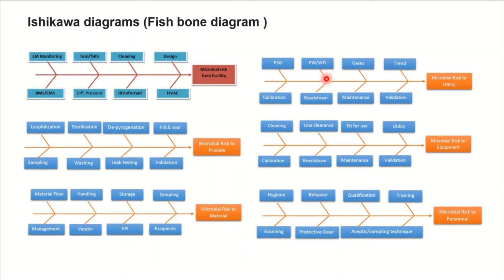For purified water (PW) and WFI: in solid oral dosage, PW is the water source for processing; for injectable processes, the final rinse should be WFI to minimize introduction of bioburden into the product, and your formulation solution should also be WFI. Steam quality is an important factor — steam is utilized for SIP of your vessels, lyophilizer chamber, and in the sterilizer.